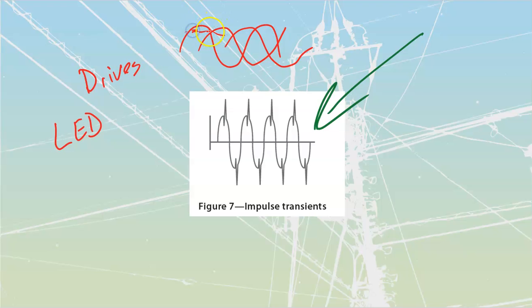Right now, that waveform is going to be supplying power, and then it shuts off. Then the next waveform supplies power, and then it shuts off. Only when it crosses, during our line-to-line rectification, when we cross that line, do we actually pass current. So this phase delivers no current, no current, no current, no current. And then all of a sudden, boom, it delivers current. Then voltage gets picked up by the next phase, so that phase shuts off. Nothing, nothing, nothing, and then boom, it delivers again.